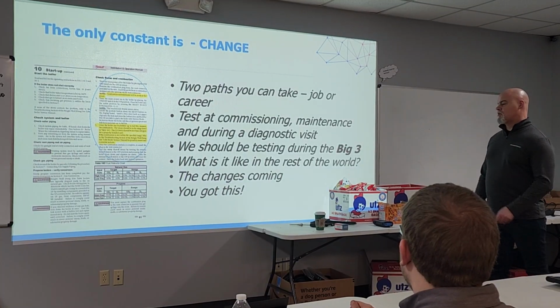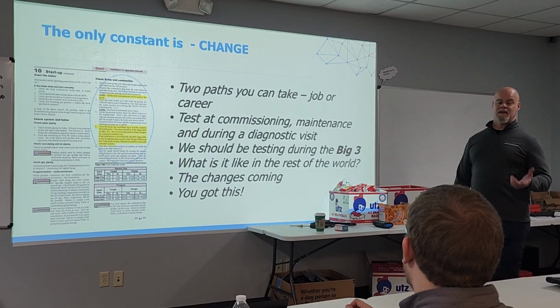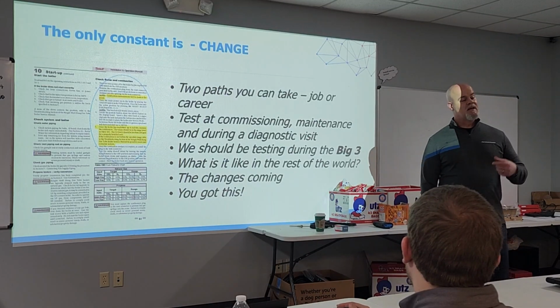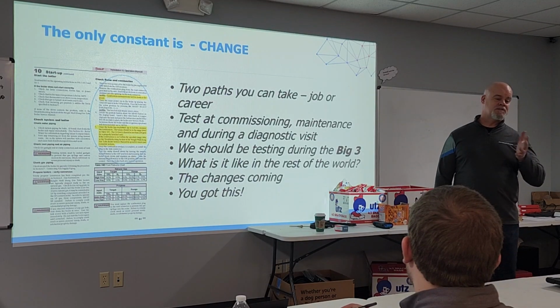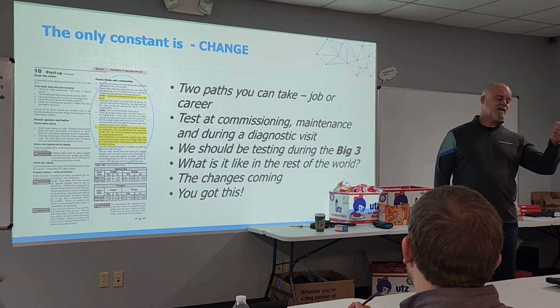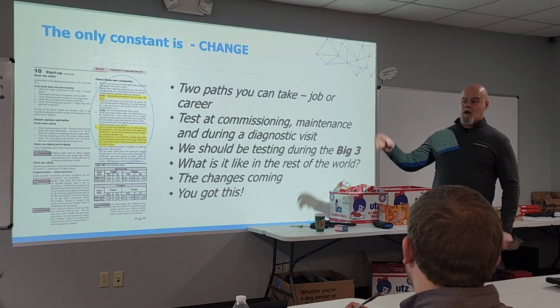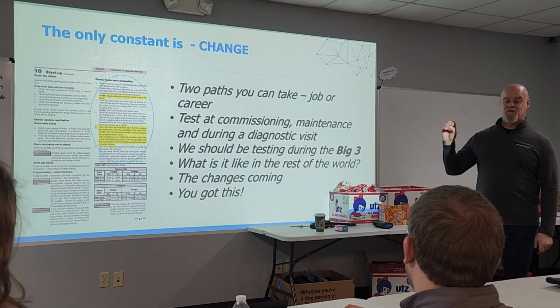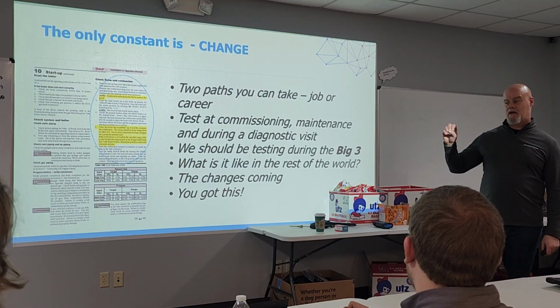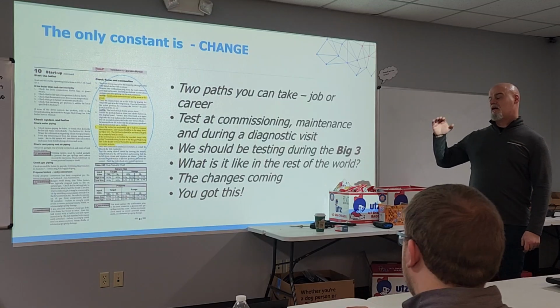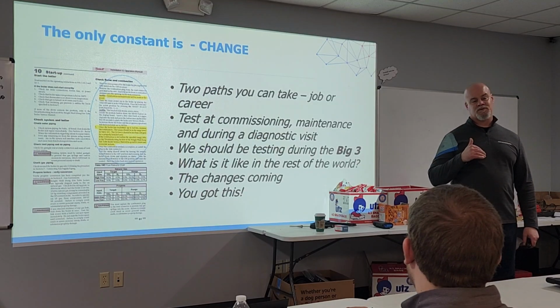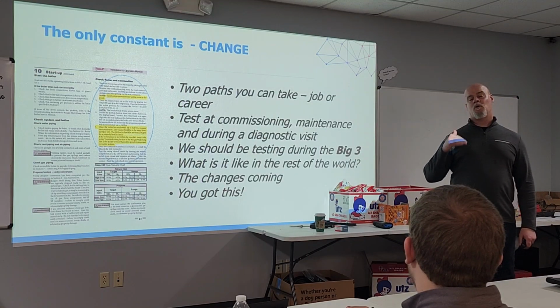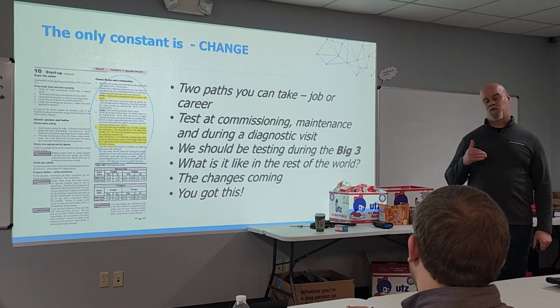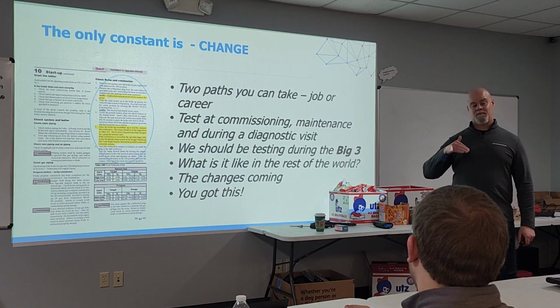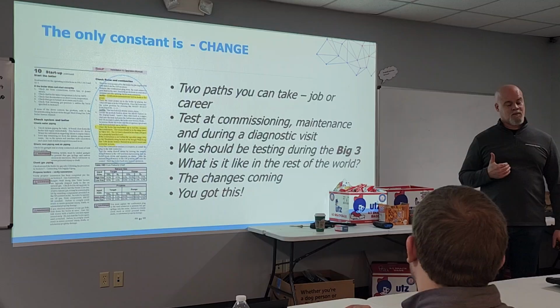What is it like in the rest of the world? The rest of the world tests predominantly because they get their fuel from Russia, and it's very expensive. In a lot of parts around the world, testing is mandatory, at least once per year. They commission with an analyzer, and they diagnose with one. Because they test as frequently as they do, their warranty claims are about 3 to 4%. Here, our warranty claims are anywhere from 20 to 35%, much higher, because we're not all testing like we're supposed to.